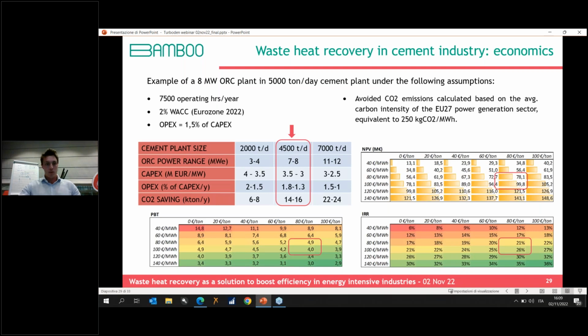According to these numbers, we can see that in this type of cement plant, typically the ORC power ranges from 7 up to 8 megawatt gross, depending on several factors like the exhaust gas temperature, like the fact that you are recovering both from preheater or from the clinker cooler, and also on the average ambient temperature of the site.